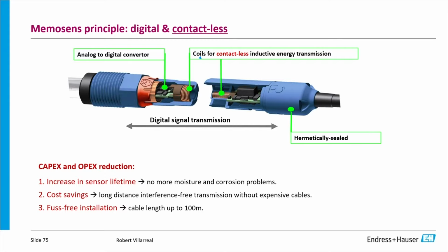To resolve this, what we've done is basically we've made a digital connection with the sensor and the cable. So Memosens technology solves these problems. If you look at the image here, both the sensor side on the left and the cable side on the right are fully hermetically sealed connectors. There are no exposed connection points, no exposed pins. They're both kind of plastic housings. So this prevents any water ingress or corrosion problems at the point of the connection. We use inductive coupling between the sensor and the cable to provide power and signal transmission. So there's no wiring that occurs when you plug in the sensor. It's a simple kind of quarter turn connection, and you don't have to worry about damaging pins.